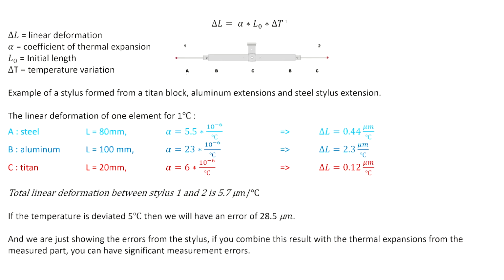Okay, so this is the formula of linear deformation. In order to better understand it, I have explained every element that makes up the formula right here. So we have the delta L, the linear deformation. We have the alpha, the coefficient of thermal expansion, L0 the initial length, and delta T the temperature variation. Okay, so the example is formed from an architecture of 2 styluses. They are formed from a titanium block in the middle, aluminum extensions right here, and stylus extensions right here. The linear deformation for one element for 1 degree Celsius is calculated like this.